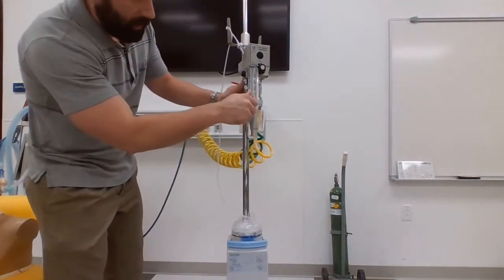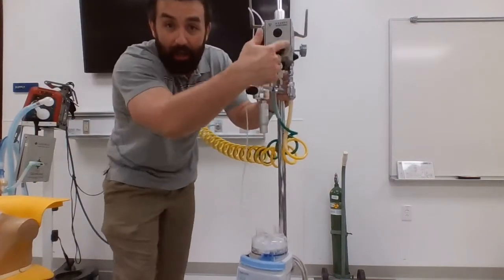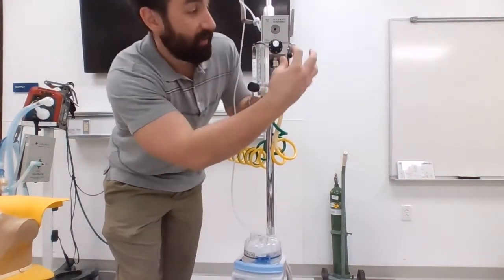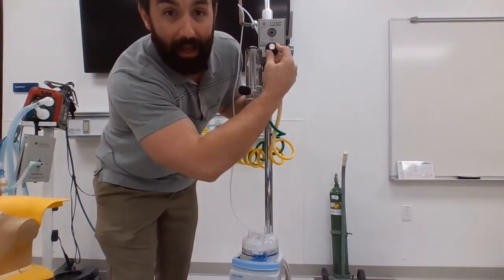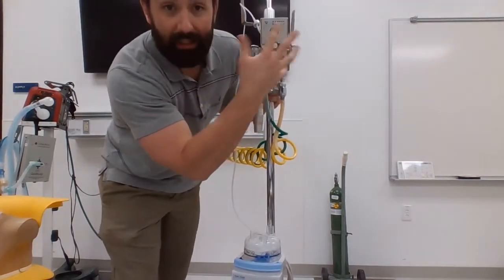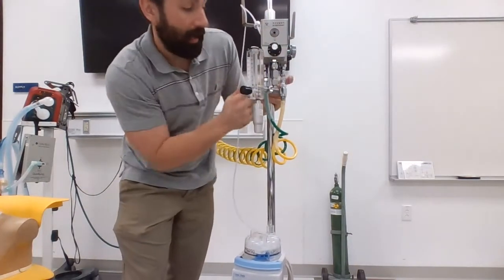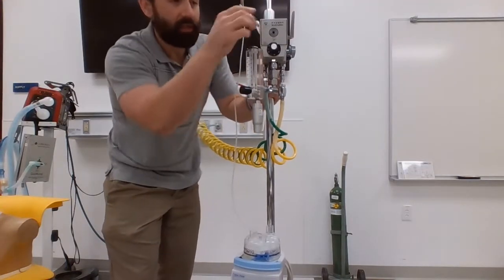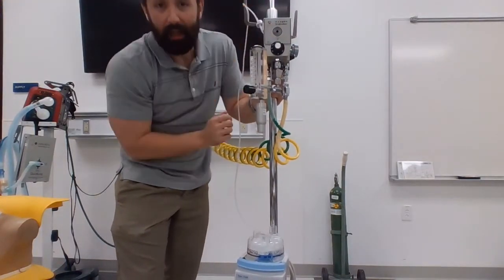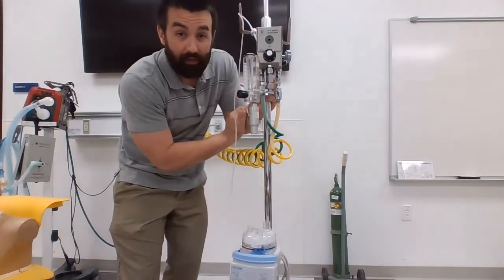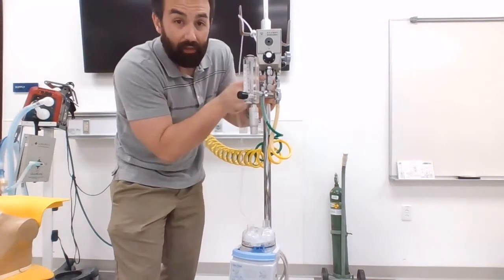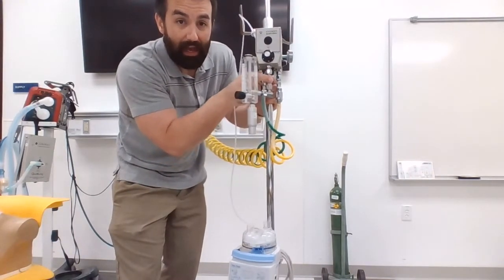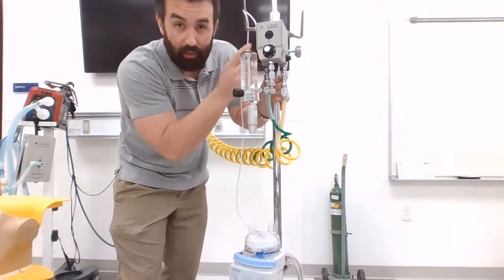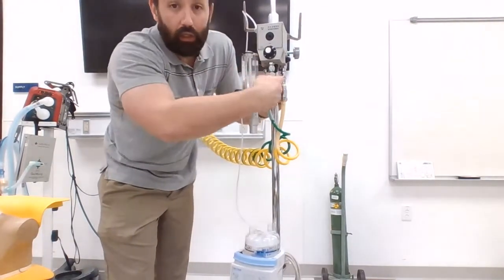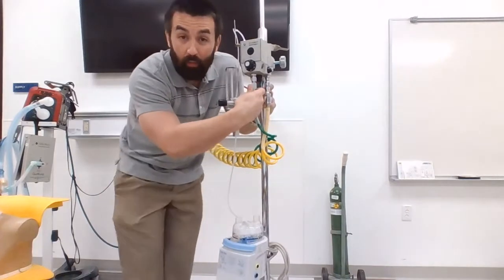So I'm all hooked up and ready to go here. So I got my blender, and it's hard to see in this video, but ultimately there's a little knob, and it's got FiO2s chosen. So I can set my FiO2, and ultimately I have two 50 psi sources of air and oxygen. I can precisely set an FiO2 by turning this knob appropriately, and then everything that comes out of here is 50 psi, at whatever FiO2 I have set. So you could hook this up to a ventilator if we wanted to, but we don't need to anymore.